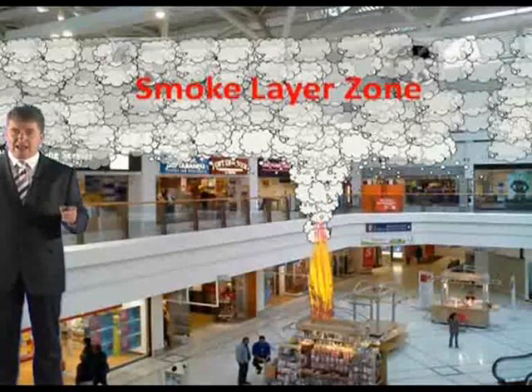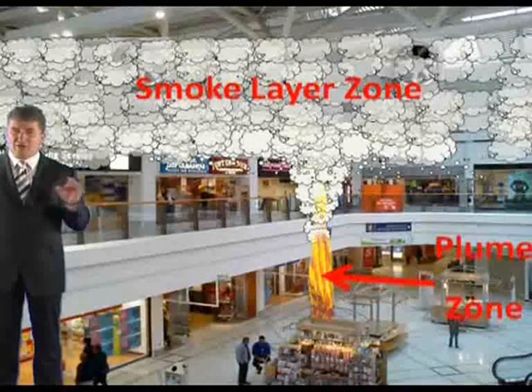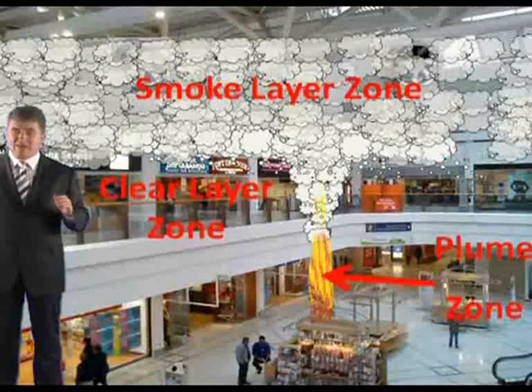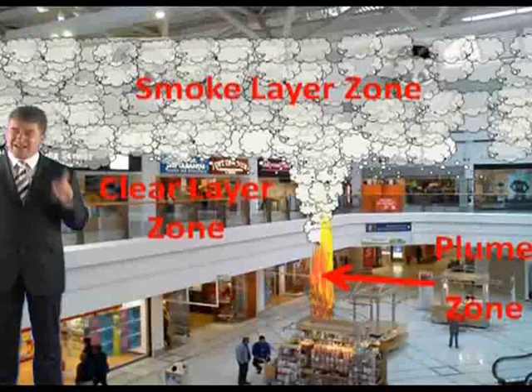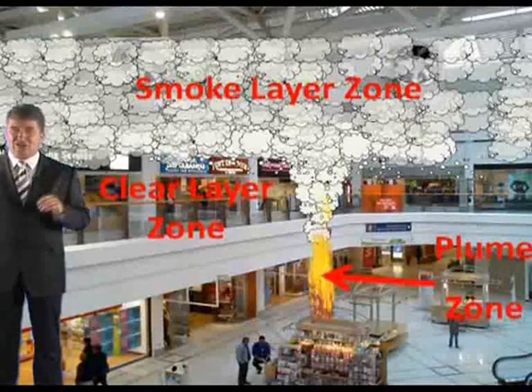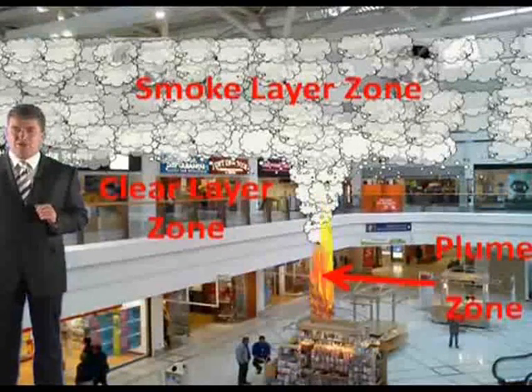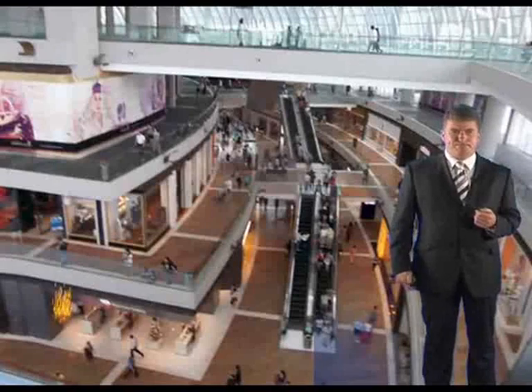The smoke layer, the plume and the layer of clear air beneath the smoke layer are viewed as being 3 separate zones, as you can see here. 3 separate zones. Now, that covers a basic design for most situations, and the plume is considered to be a simple plume because it originates in the compartment where you're actually exhausting all the ventilation. That's where the fans are, and the extraction is where the fire is. That's called a simple plume.